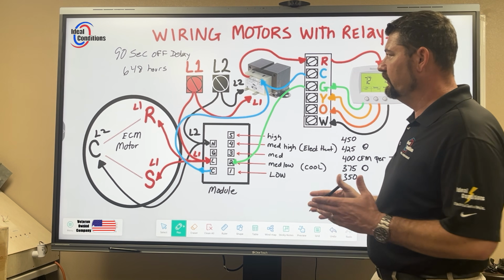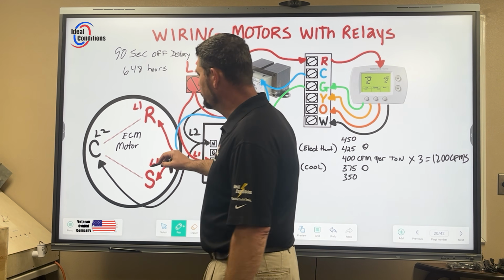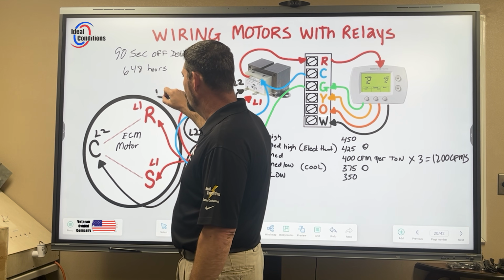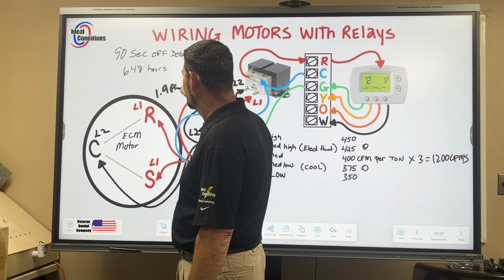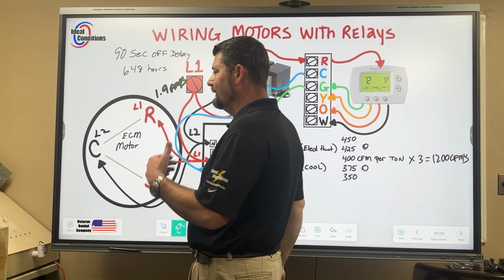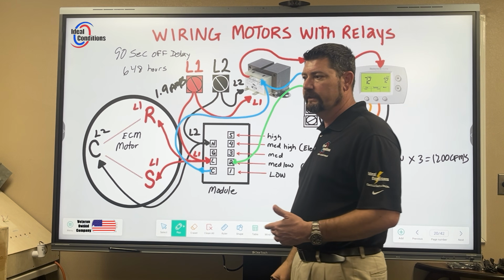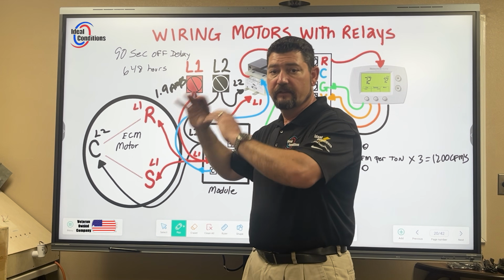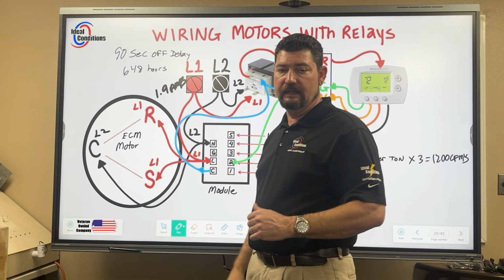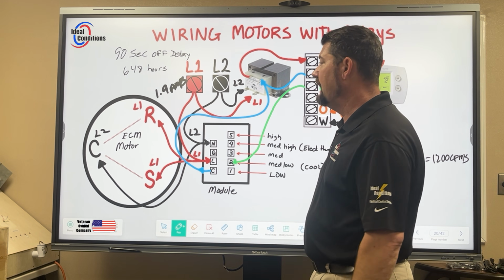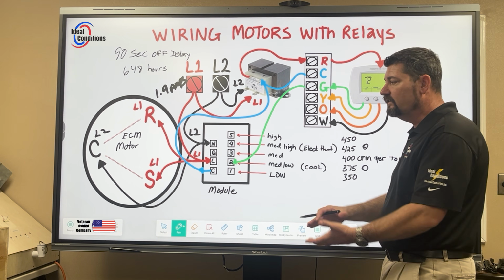And out of that, that's 648 hours that, if this is only running at, say, 1.9 amps of electricity, is a lot cheaper to give you heat and cooling than the additional 12 to 18 amps that the condenser is going to be adding to that equation. And so that's the efficiency they're getting.